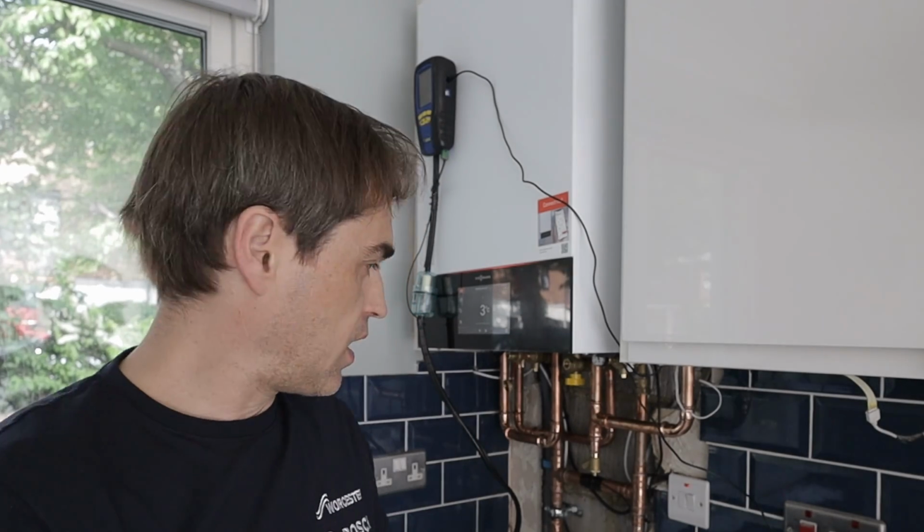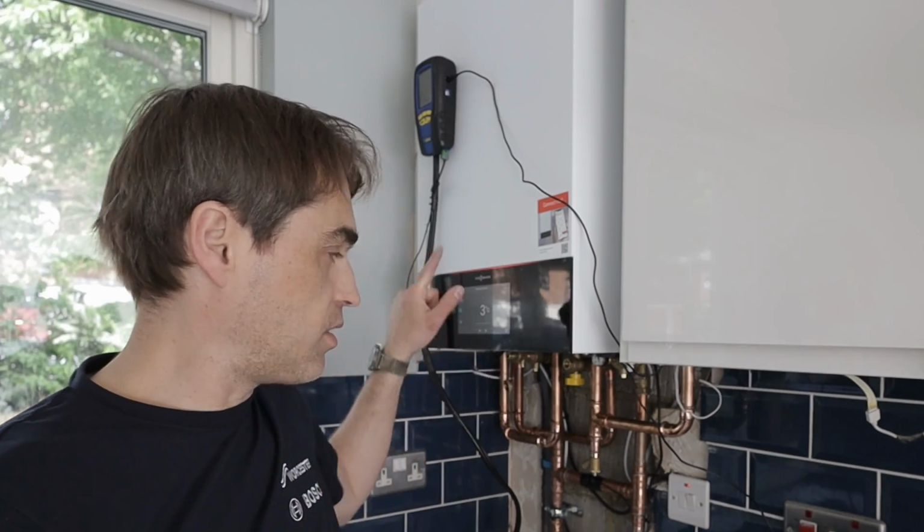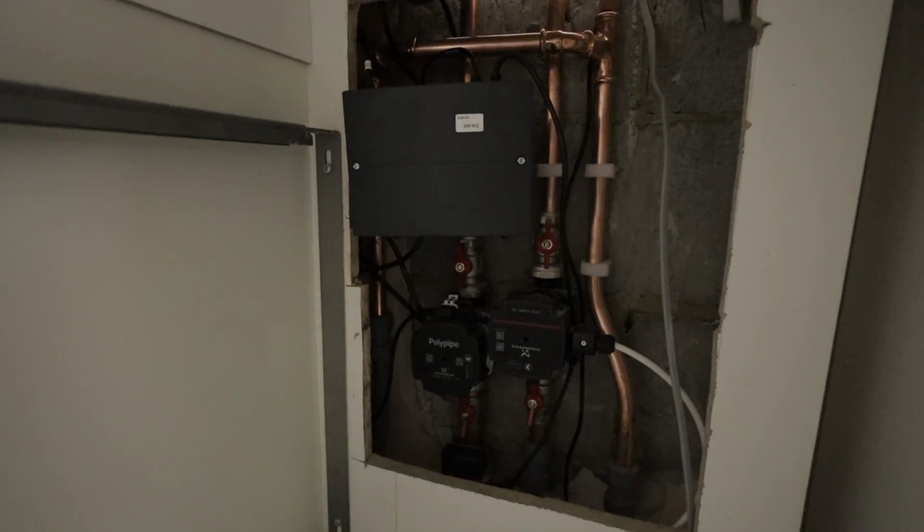The reason being, I've got underfloor heating on a mixed circuit, so it blends flow and return to lower the temperature of water, and an unmixed circuit on radiators on a pump. And I've got a separation here, close coupled T's, so pumps don't pull on each other. So one pump circulates in a boiler and does hot water, another pump does underfloor heating, and yet another pump does radiators. To do that, however, I was told I'd need 2 modules, mixed and unmixed modules.